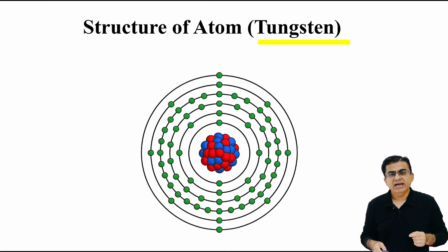Second, tungsten has an incredibly high melting point of 3000 degrees Celsius. I will remind you of what we discussed in the previous lecture. I showed you that over 99% of the kinetic energy from the electron beam is wasted as intense heat. Most normal metals would simply melt or get destroyed under this extreme heat. Because tungsten can easily withstand this intense heat without being destroyed, it is the perfect target material for our X-ray tube.